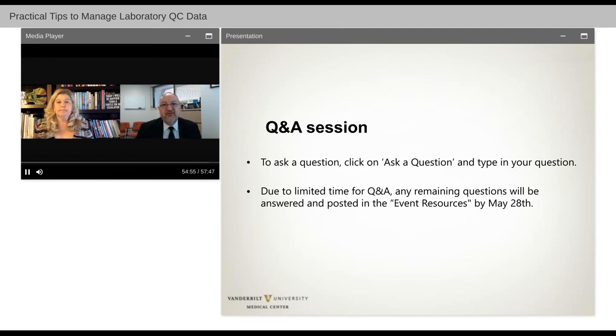But then you can go with a frequency that is based on your local requirements. In the United States, it's based on CLIA regulations, and you need to basically run quality control for non-waived methodologies, run at least two levels each day of patient testing. Or you can develop, through risk management, an individualized quality control plan that will allow you to reduce the frequency of QC in lieu of some built-in or internal processes that are present on a lot of our point-of-care testing methodologies. So it's dependent on the method, dependent on your local regulations, but typically it is a minimum QC once a day, or using an alternative like risk management to reduce that frequency. Two, weekly, monthly.